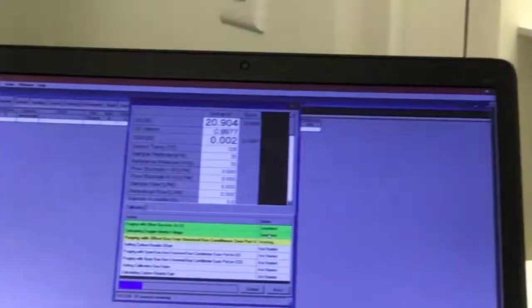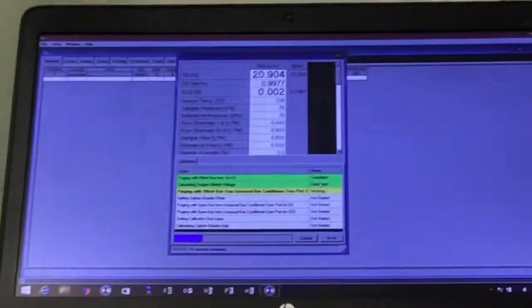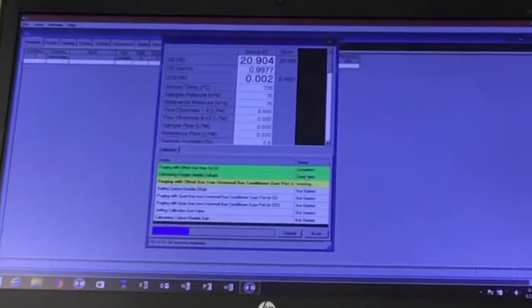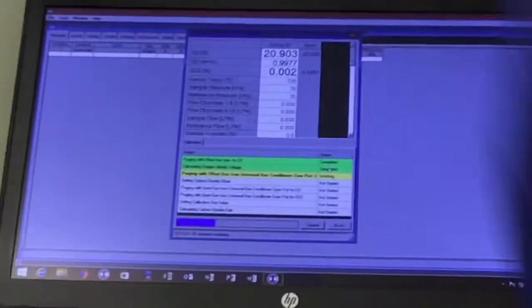So the other thing is that calibration can be done while you have your animals inside the cages. The cages have nothing to do with calibration. The only thing it is reading is the reference inside, when there's no animal in the black box. So calibration has nothing to do with your actual cages. You can be in there petting your animal, giving food, doing everything. You can do everything else while it's running.